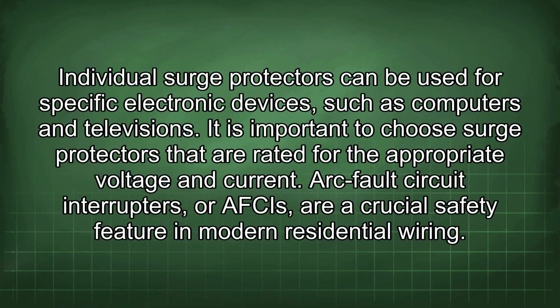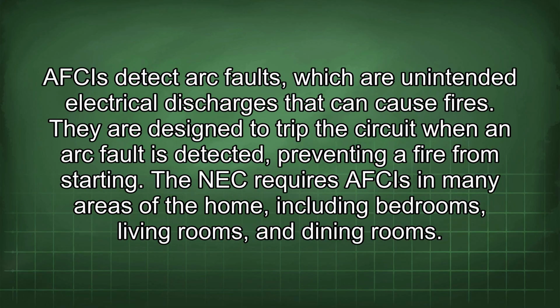Arc fault circuit interrupters, or AFCIs, are a crucial safety feature in modern residential wiring. An AFCI detects arc faults, which are unintended electrical discharges that can cause fires. They are designed to trip the circuit when an arc fault is detected, preventing a fire from starting. The NEC requires AFCIs in many areas of the home, including bedrooms, living rooms, and dining rooms.